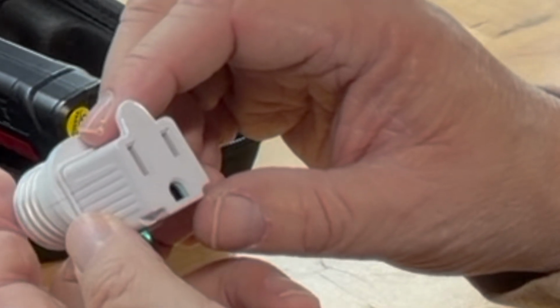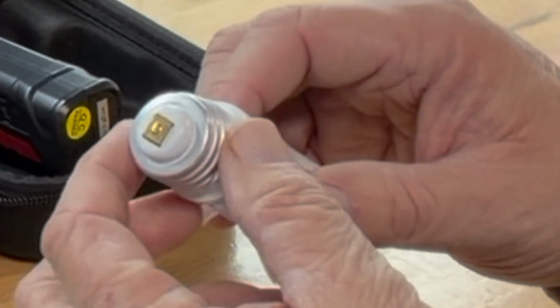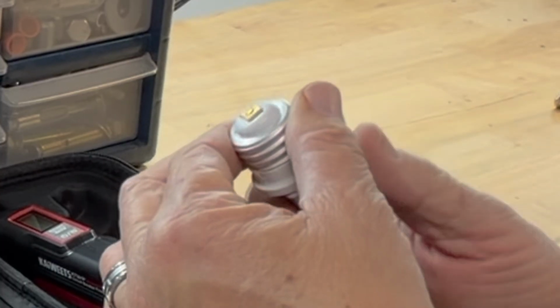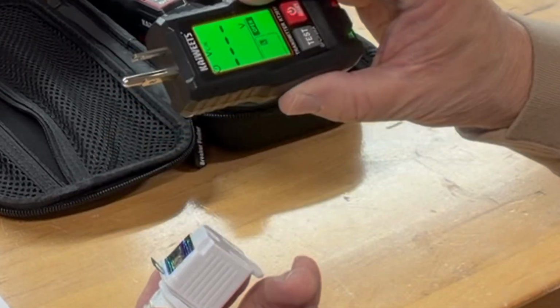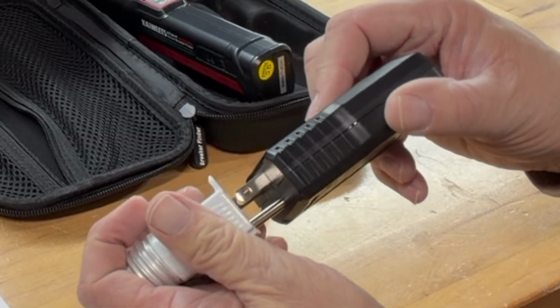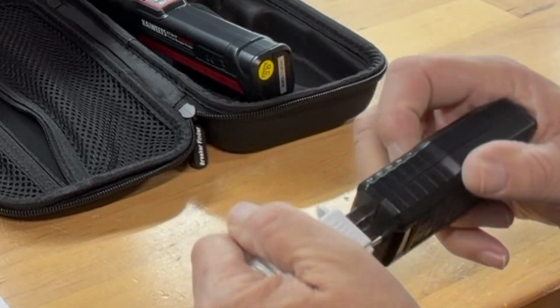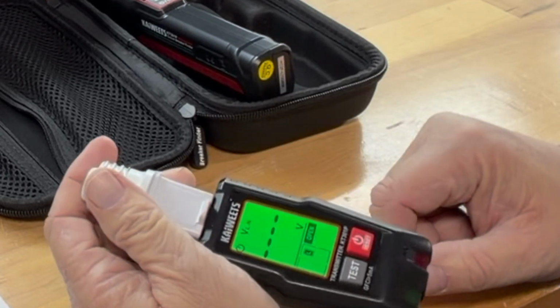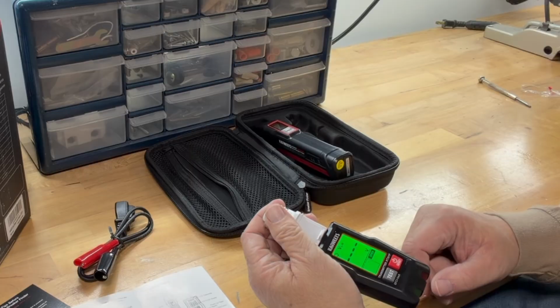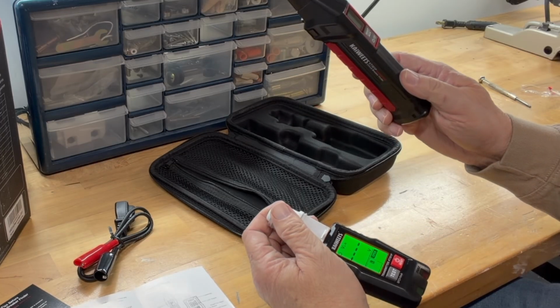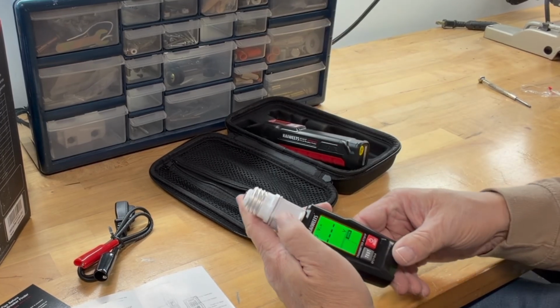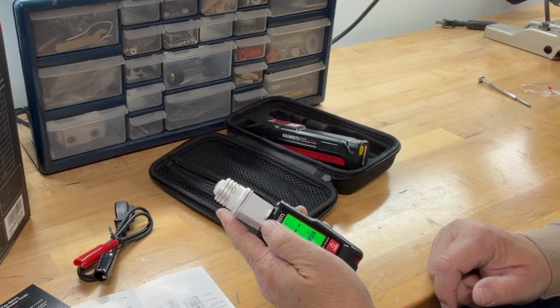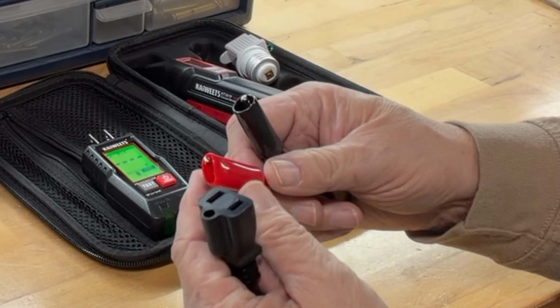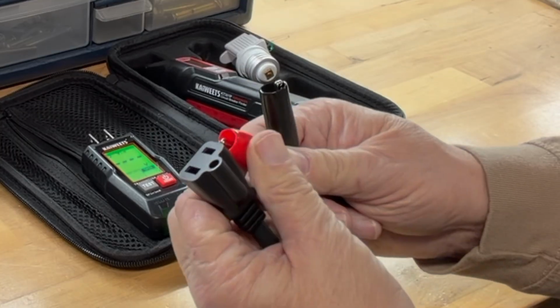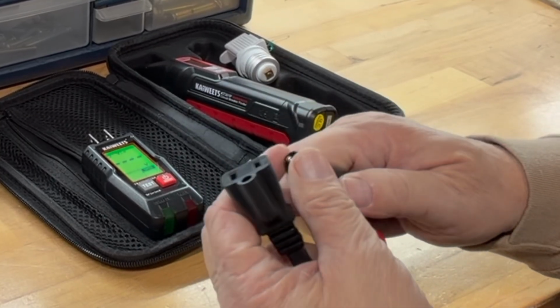And this light socket adapter is just like anything where you would screw in a light bulb. You would just screw this in the place of where the light bulb is, and then just take your tester here, plug that in, and it should indicate voltage. And then you could use this on your breaker to indicate where the breaker is that feeds into this particular circuit. Likewise, if you had some bare wiring, you have positive alligator clips and negative alligator clips.